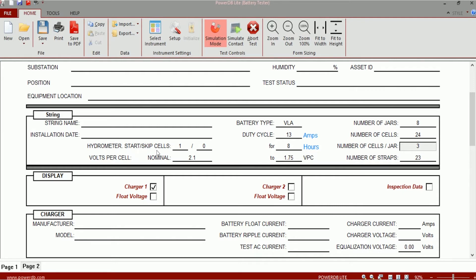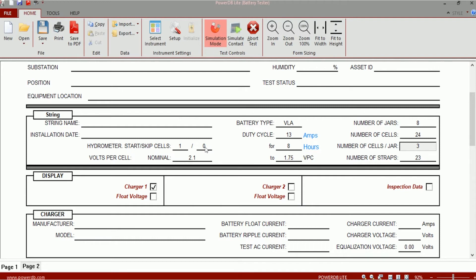Hydrometer start skip cells is for you to be able to modify the specific gravity column according to the way in which you're going to be taking measurements. So if you're not going to take specific gravity measurements on every cell or every jar on the battery string, then you can enter the number of cells or jars that you would like to skip.